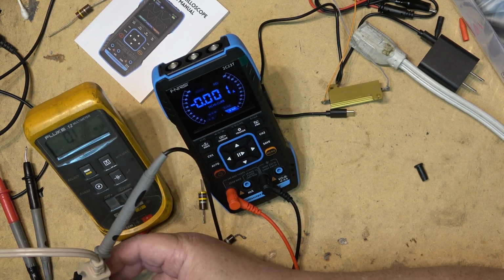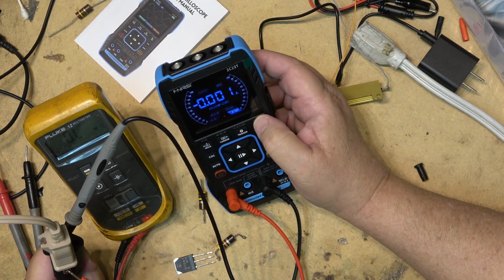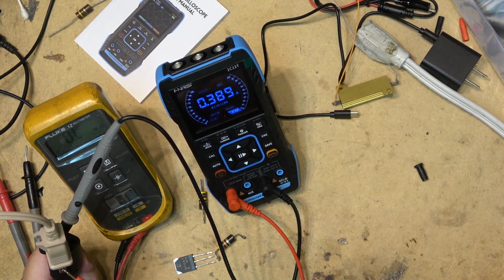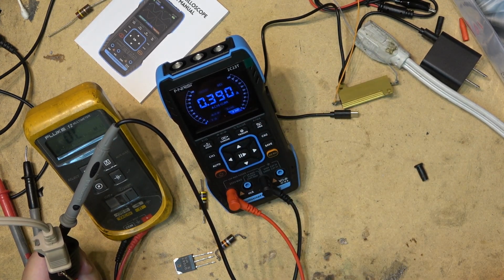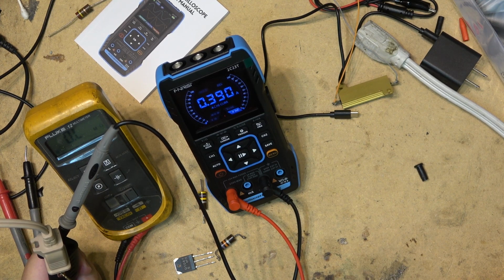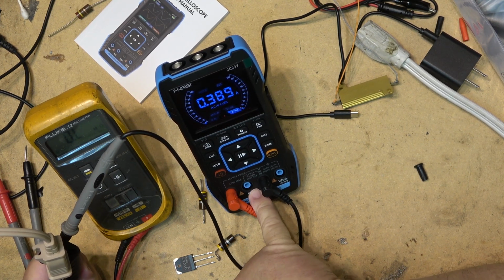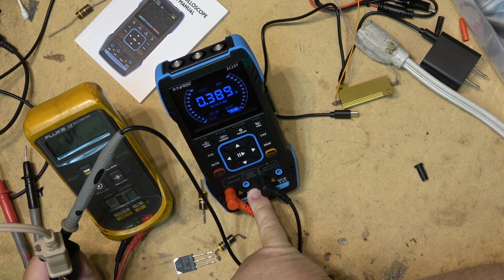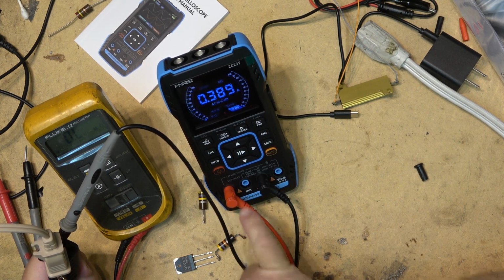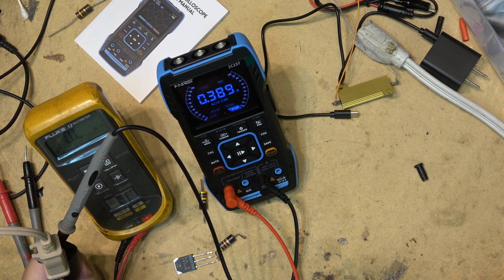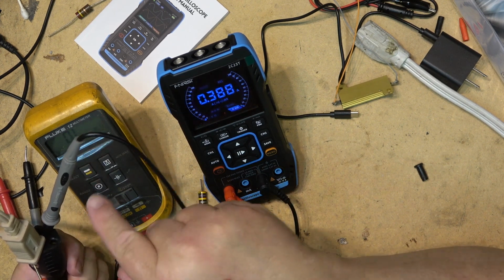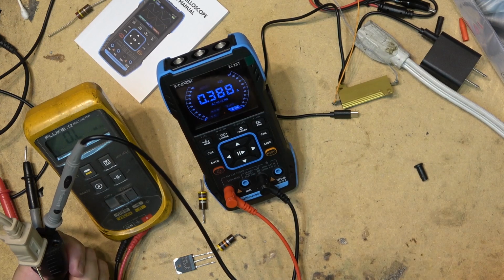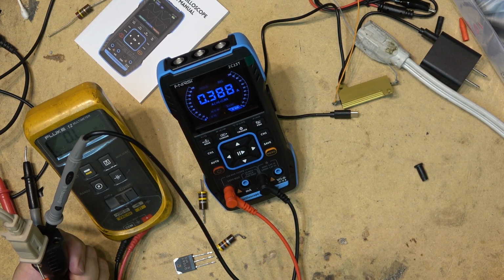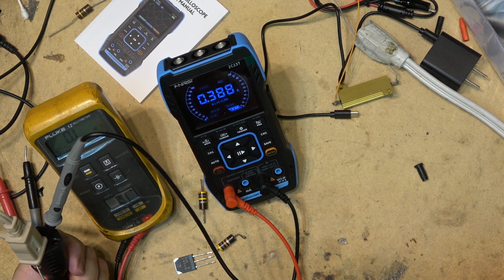Let's make sure we're in AC, AC high current. 389, 390 milliamps. So there's a mA setting, fused at 1 amp, that measures in milliamps, or in this case I'm measuring high current, which goes up to 10 amps. The power flows through the leads, through the meter, and back. That's current measurement, and it's accurate since we've measured this fan before.